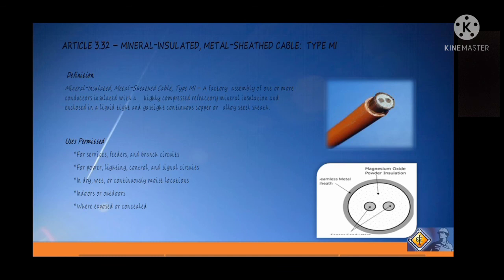Next, in Article 3.32, which is the mineral insulated metal sheathed cable or the type MI. The type MI is a factory assembly of one or more conductors insulated with highly compressed refractory minerals and enclosed in a liquid-tight and gas-tight continuous copper or alloy steel sheath. Makita natin yung itsura ng ating type MI and ang kanyang components. So we can see the seamless metal sheath and the magnesium oxide powder insulation.